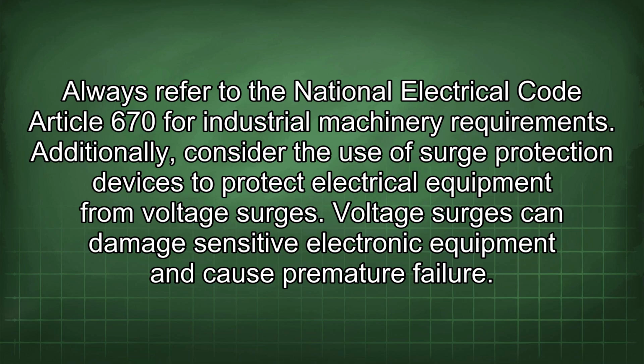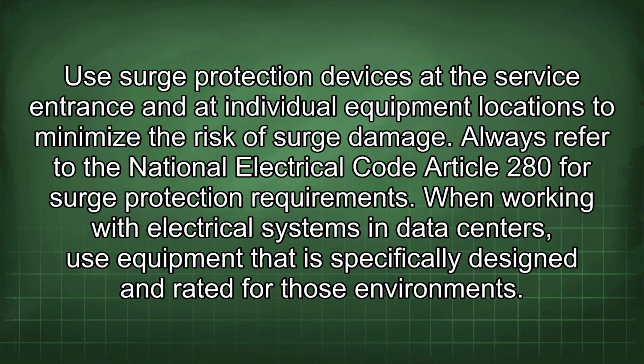Additionally, consider the use of surge protection devices to protect electrical equipment from voltage surges. Voltage surges can damage sensitive electronic equipment and cause premature failure. Use surge protection devices at the service entrance and at individual equipment locations to minimize the risk of surge damage. Always refer to the National Electrical Code Article 280 for surge protection requirements.